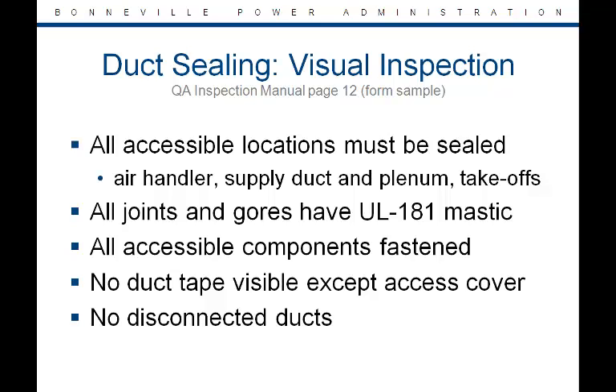All joints and gores must have UL 181 mastic, and all accessible metal duct connections must be fastened with a minimum of 3 sheet metal screws. No duct tape should be visible except on the access cover, and there should not be any disconnected ducts.